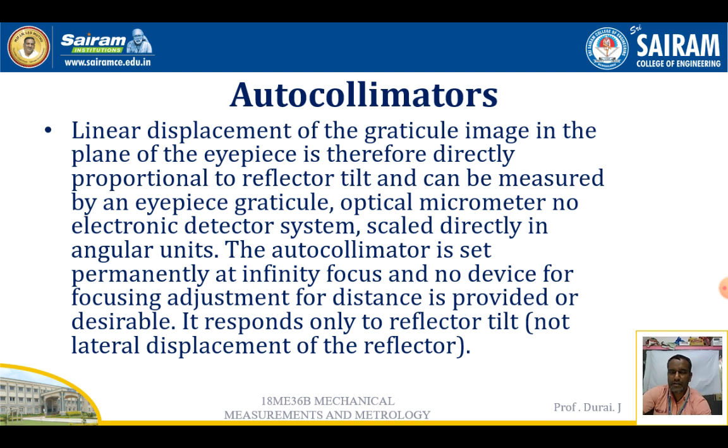The eyepiece reticle, optical micrometer, or electronic detector system is scaled directly in angular units. The autocollimator is set permanently at infinity focus. No device for focusing adjustment is provided or desirable. It responds only to reflector tilt.